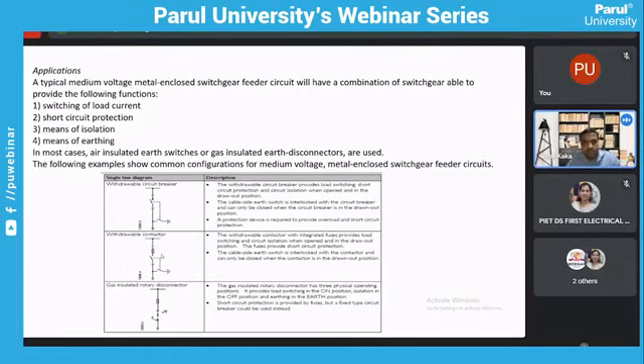Again, this is just an application in terms of withdrawable circuit breakers and withdrawable contactors. A withdrawable circuit breaker provides load switching, short circuit protection, and circuit isolation when open and in the drawout position. The cable earthing switch, which is interlocked with the breaker, as I said earlier, can be closed when the breaker is in drawout position. So that's relevant to the earthing switch operation. The protection devices like relays are required to provide overload as well as short circuit protection. A withdrawable contactor with integrated fuses, as I discussed earlier, provides load switching as well as circuit isolation when open and in drawout position.